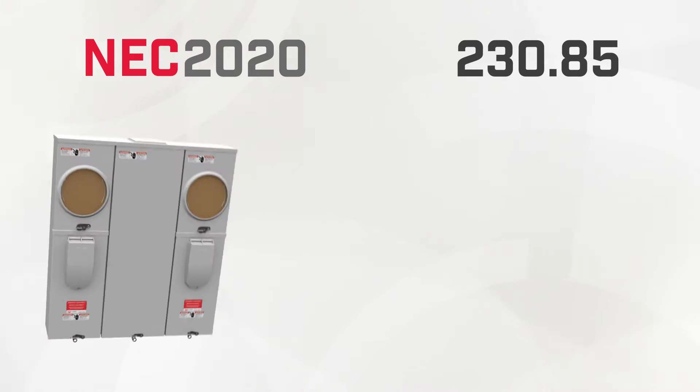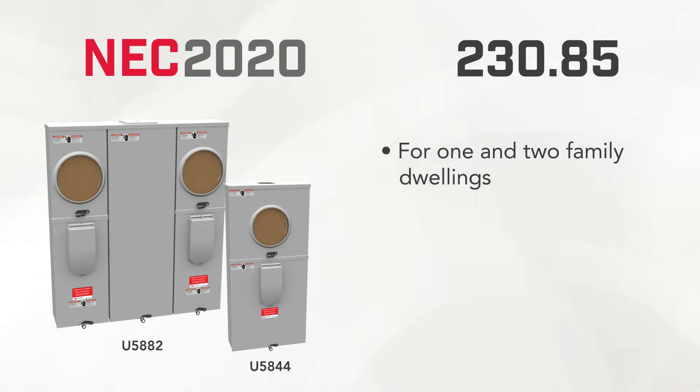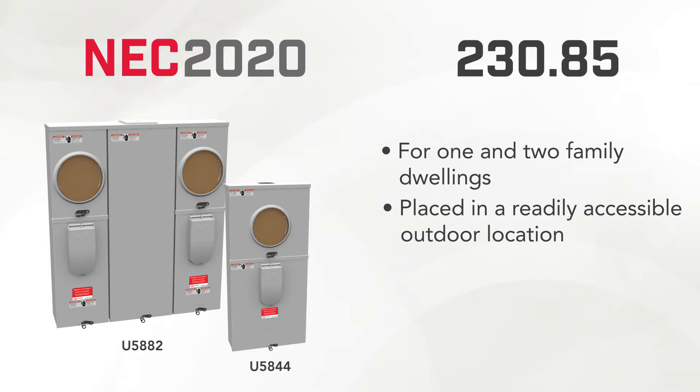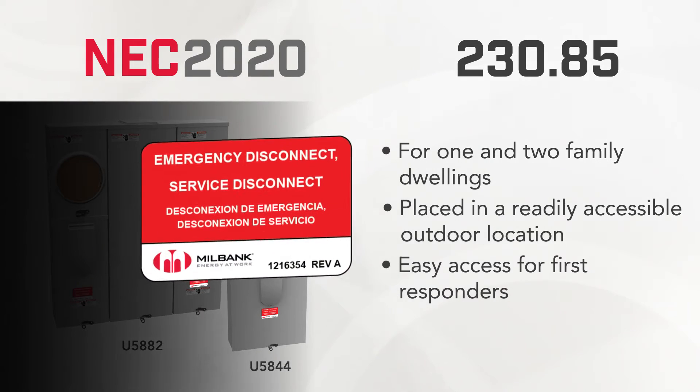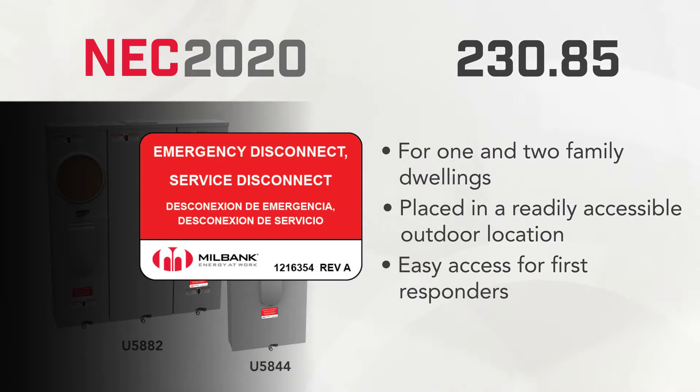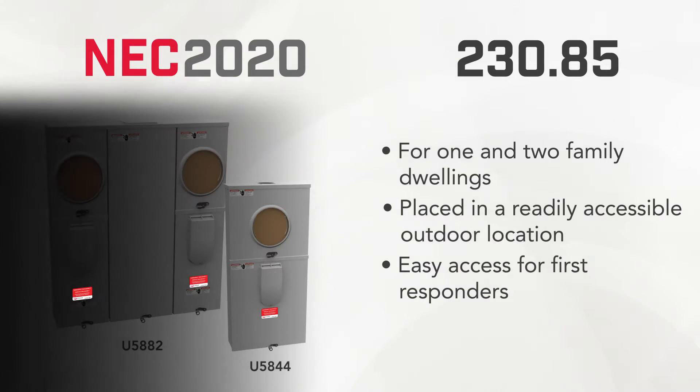This code applies to residential one and two family dwellings and is a new requirement for an emergency disconnect in a readily accessible outdoor location. This allows first responders to disconnect power to the home when fighting fires or other emergencies. The disconnect must be clearly labeled as an emergency disconnect, and Milbank supplies all meter mains with the label necessary to meet this requirement.